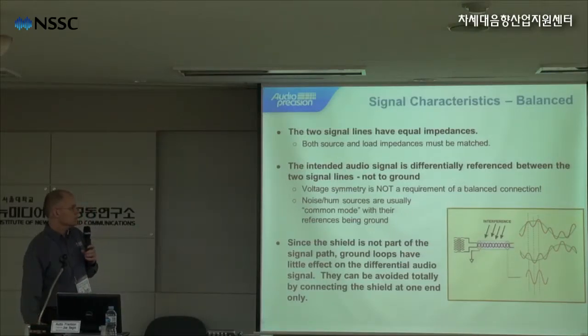This shows the characteristics of a balanced connection. In this case, the two signal lines have equal impedances. Both the source and the load impedances must be matched. Here we have a twisted pair of cable, and you can see we have the positive going signal and the negative going signal. The interface takes the difference between the two, subtracts out the noise and reinforces the signal.